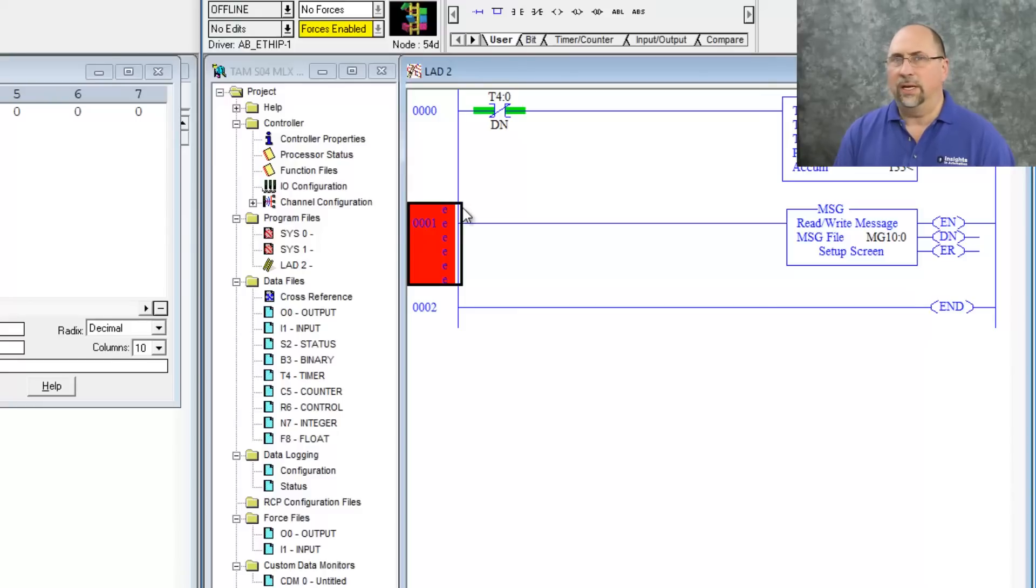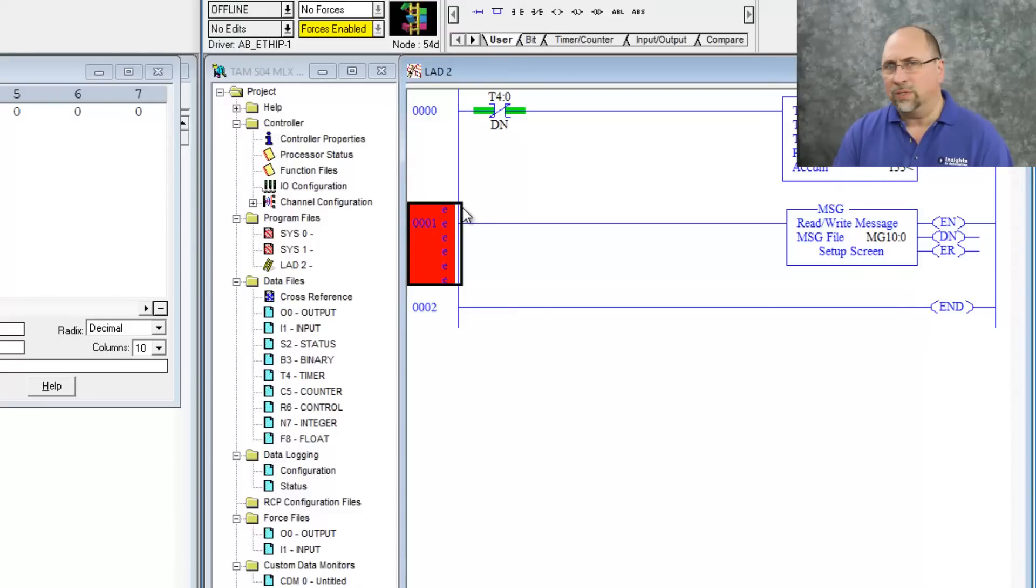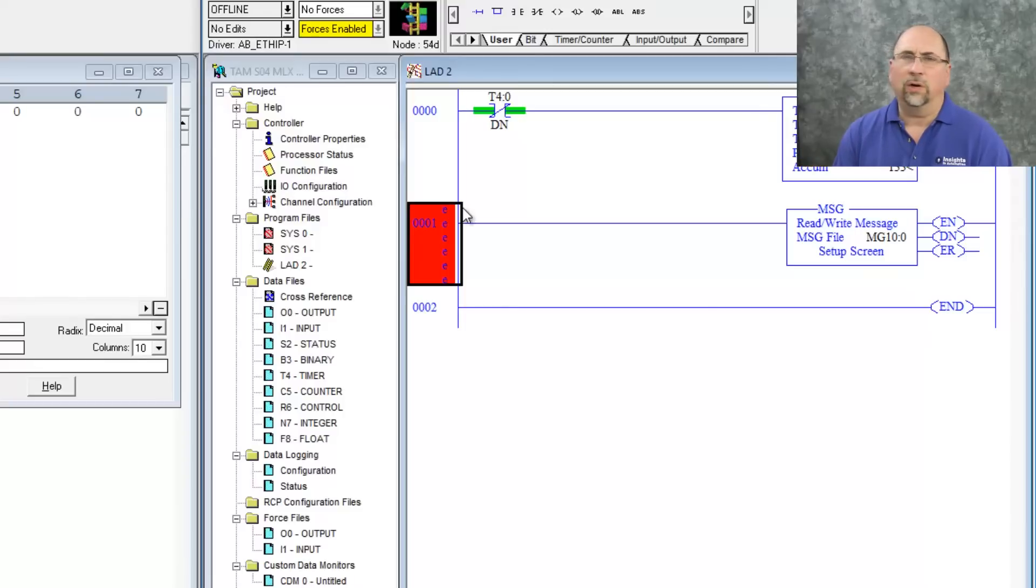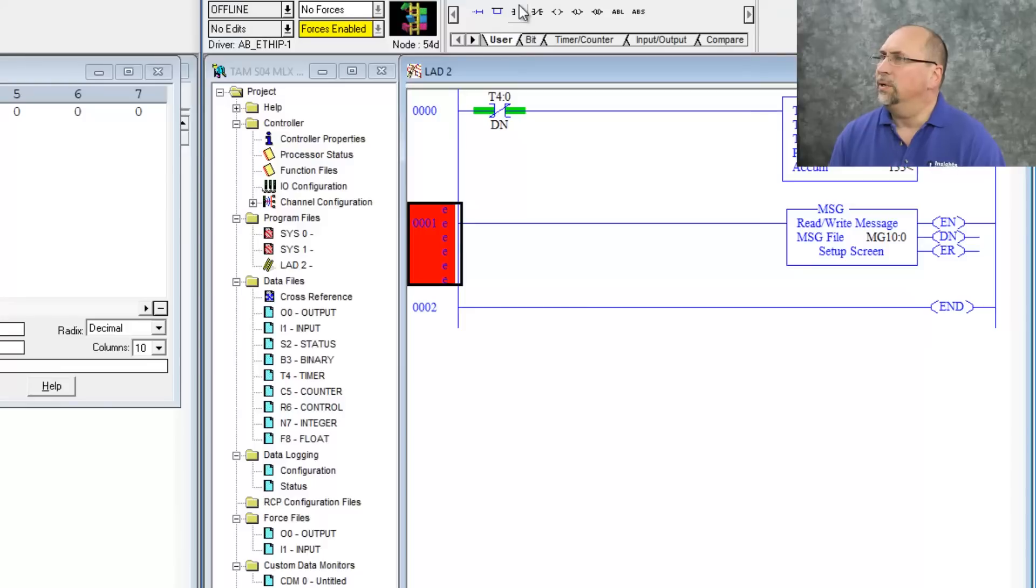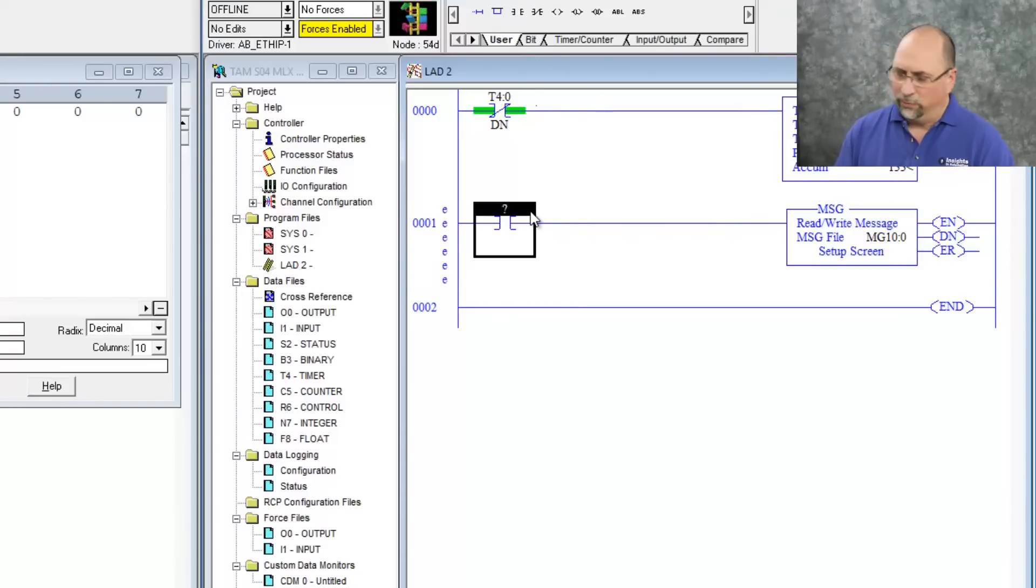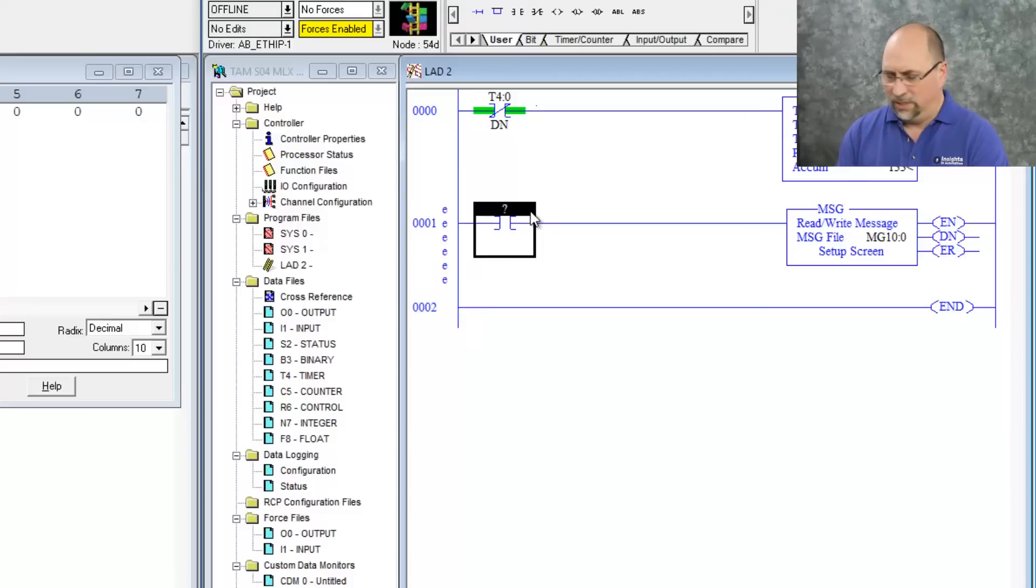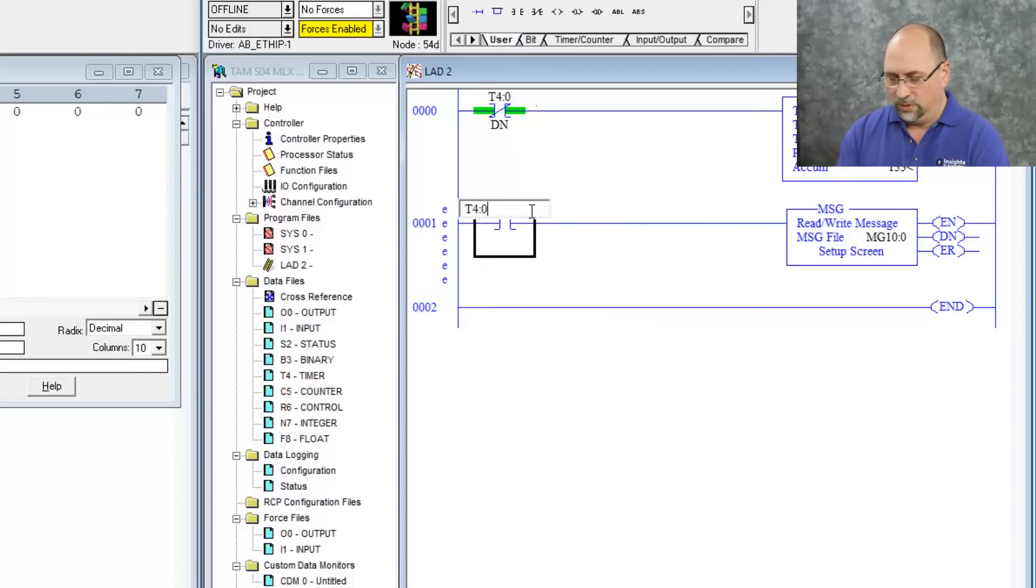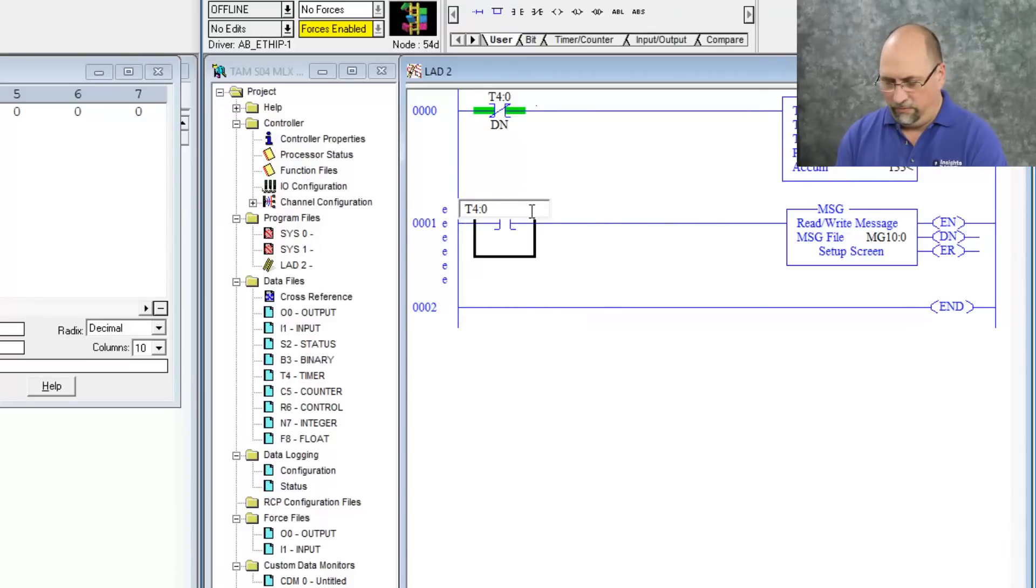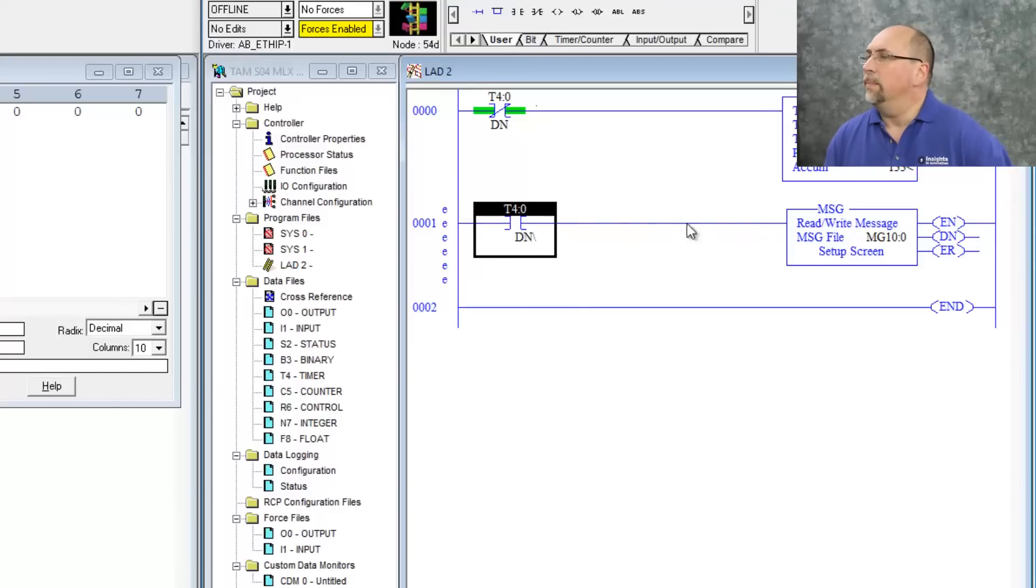So in this case, while I like to interlock my messages into a round robin when I'm doing a SCADA type system, here, I'm just going to trigger it based on a timer. I already have the timer in there. So let me go ahead and put an XIC. We've done timer in previous episodes, so I won't go over that again. But here, I'm just going to put in T4:0/DN or the done bit of my timer.